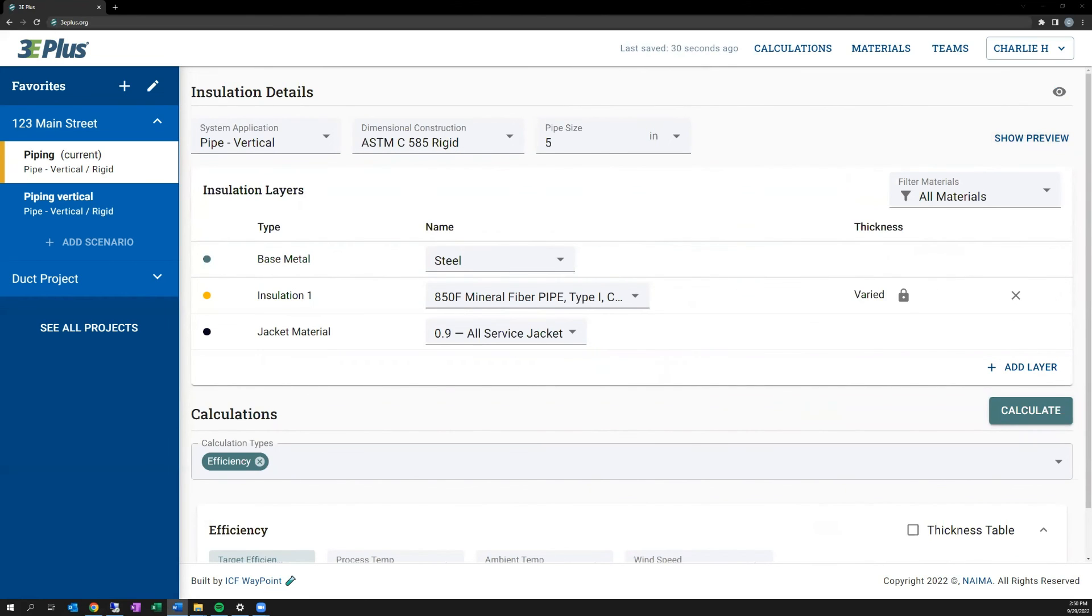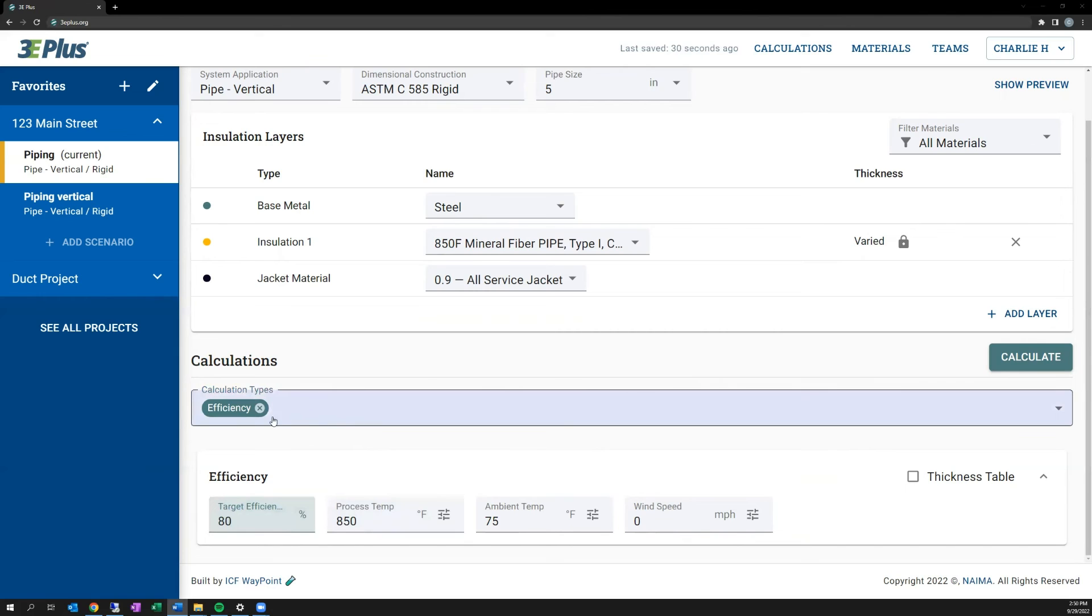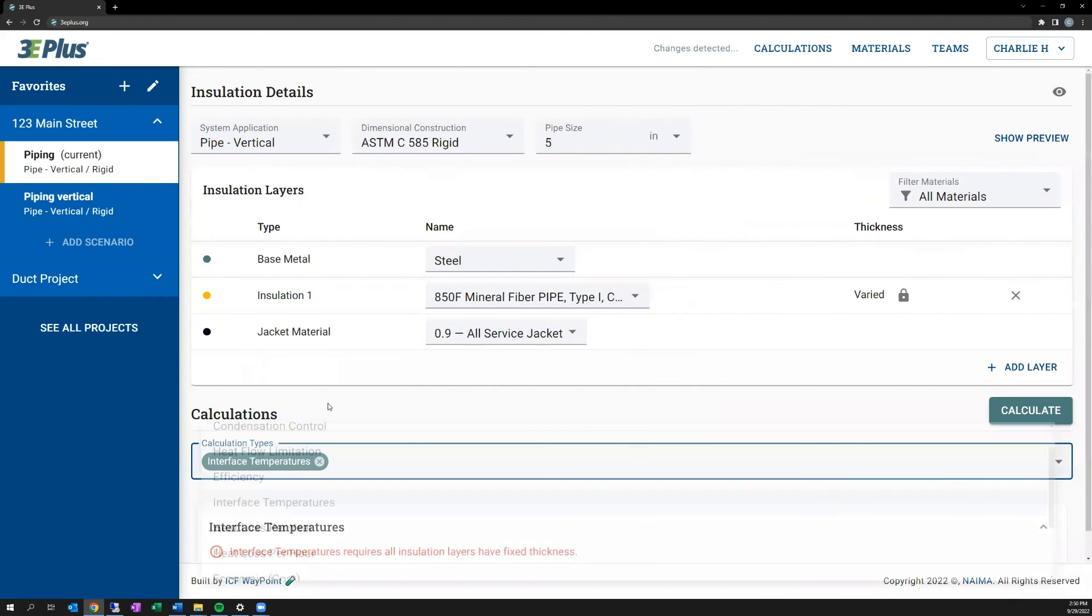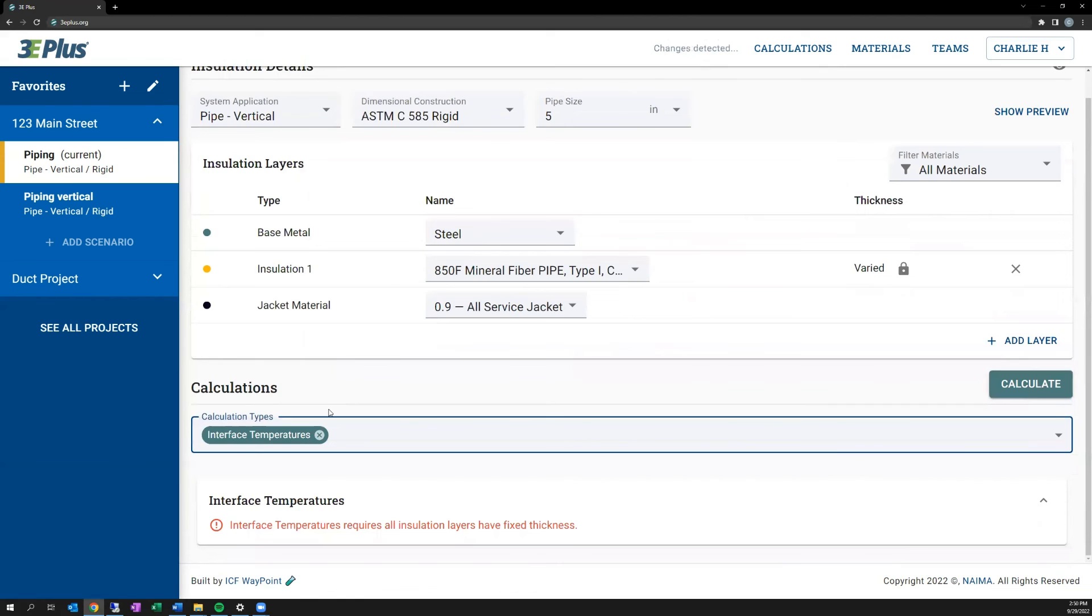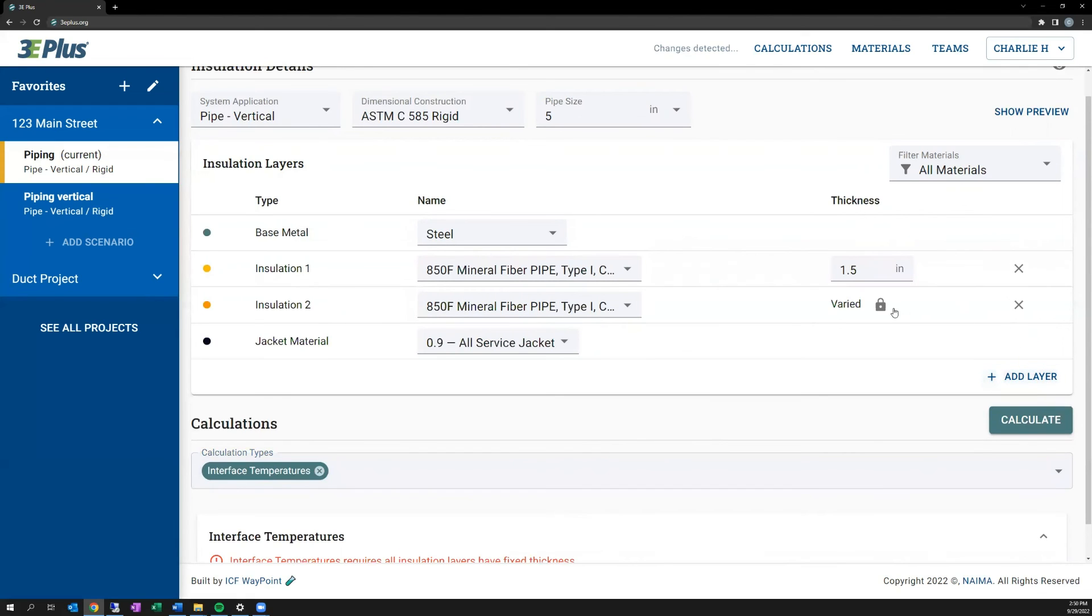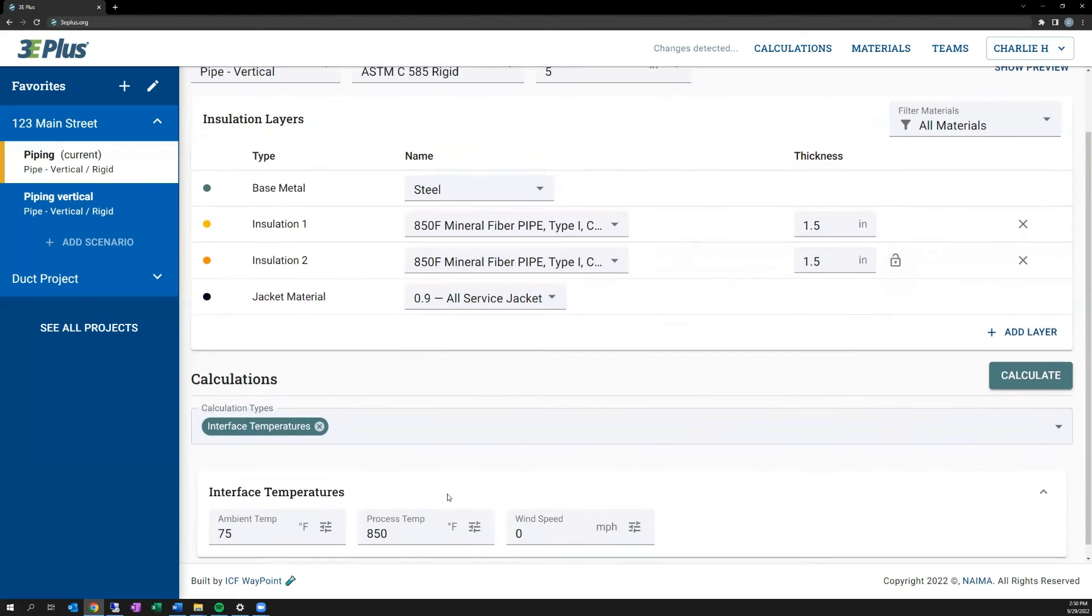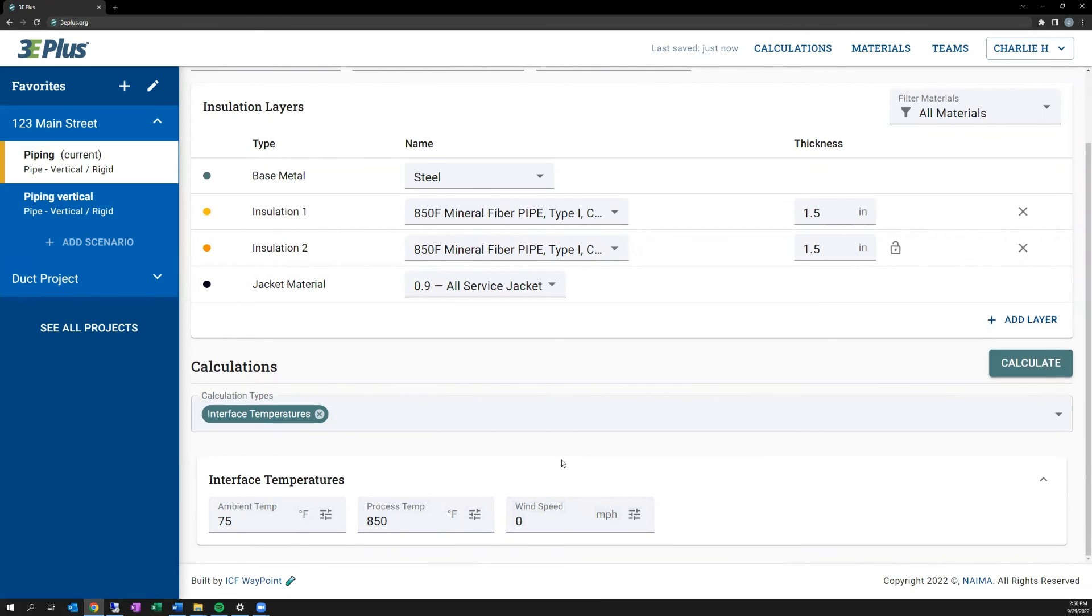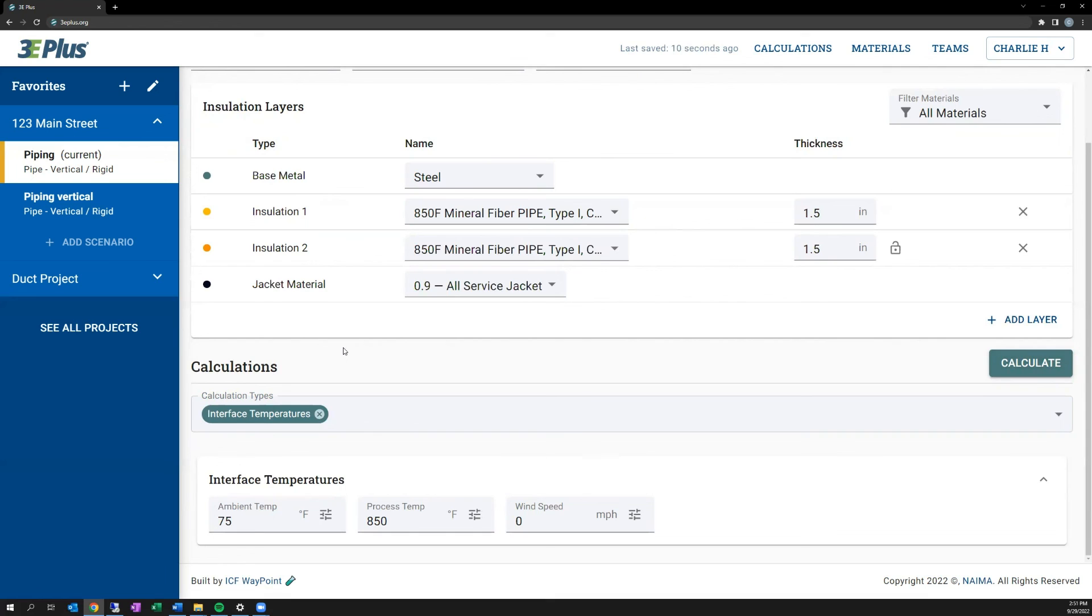So now that we've discussed target calculations, let's discuss interface temperatures. This is only relevant when you have fixed amounts of insulation, and in particular, when you have two or more layers of insulation, as noted here. So I'm going to add a second layer of the same insulation type, and they'll both be fixed amounts. I'll default to 75 degrees for an ambient temperature, a process temperature of 850, and a wind speed of zero in this case. And what this calculation does is it tells you the temperature between the pipe and the first layer of insulation, between the two layers of insulation, insulation one and insulation two, and then on the outside of insulation two.